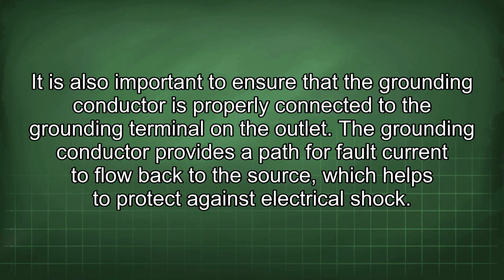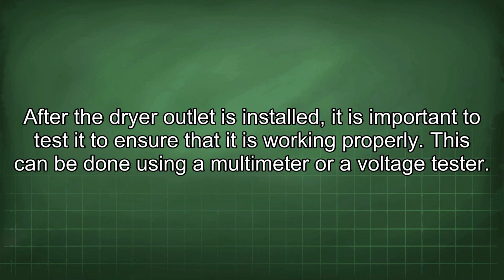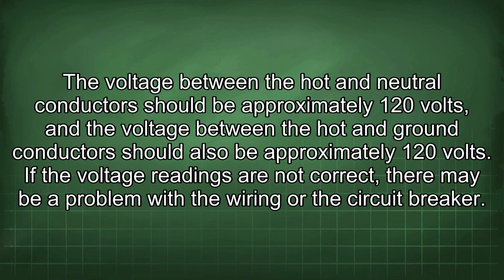After the dryer outlet is installed, it is important to test it to ensure that it is working properly. This can be done using a multimeter or a voltage tester. The voltage between the hot and neutral conductors should be approximately 120 volts, and the voltage between the hot and ground conductor should also be approximately 120 volts. If the voltage readings are not correct, there may be a problem with the wiring or the circuit breaker.